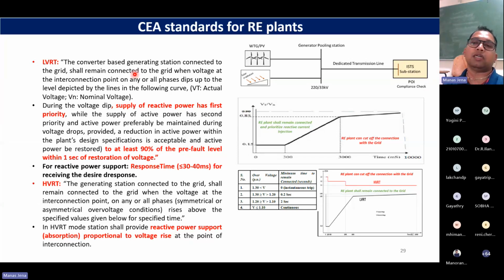So once you are under LVRT, that means you are essentially supporting the grid by providing VARs. That should be the priority. Now you have two components. One is the active component, one is the reactive component. Reactive component you are giving first priority. Then if you still have some bandwidth as far as your inverter capacity is concerned, if you still have some capacity available, you can give the active power also, no problem. But you should remain connected. So that is how this figure is telling.